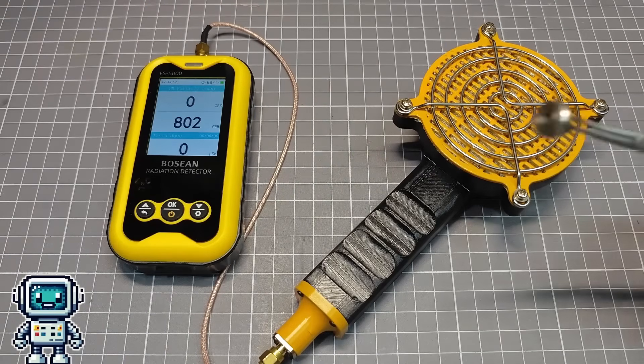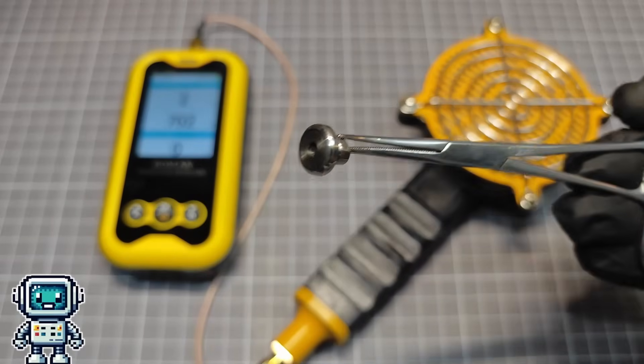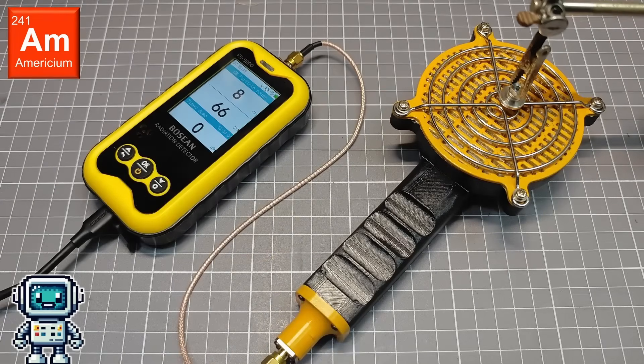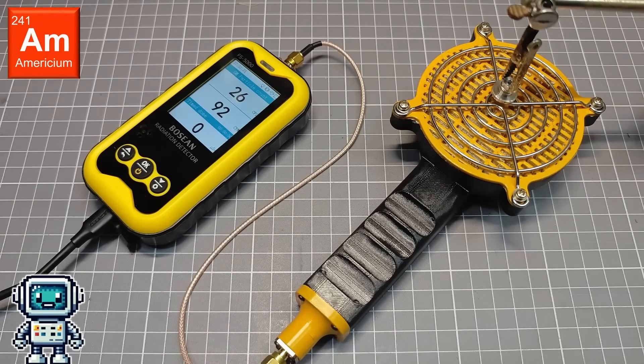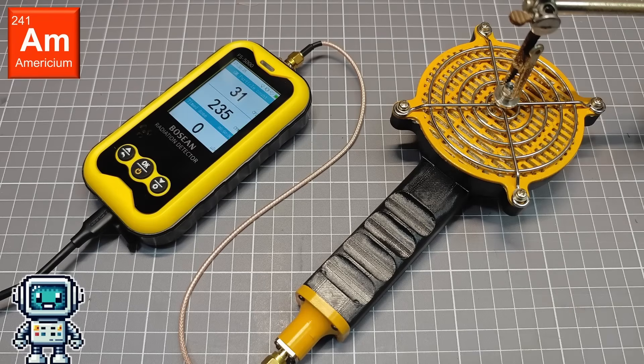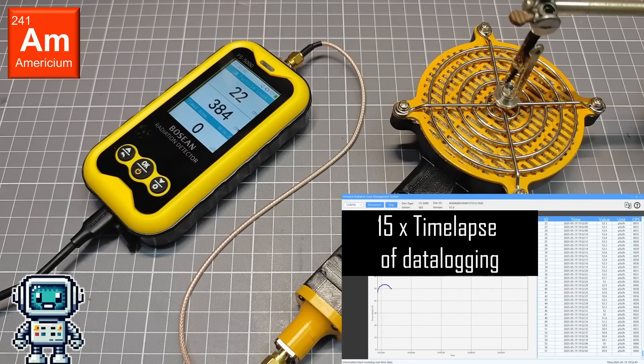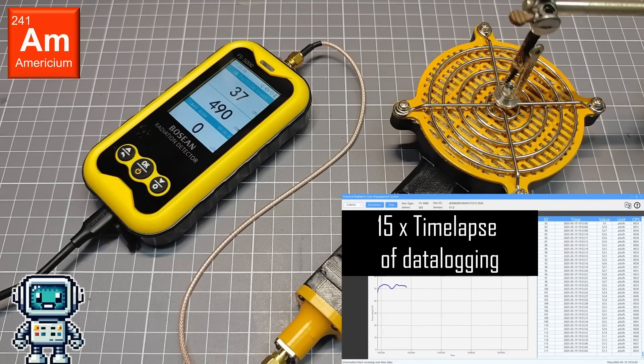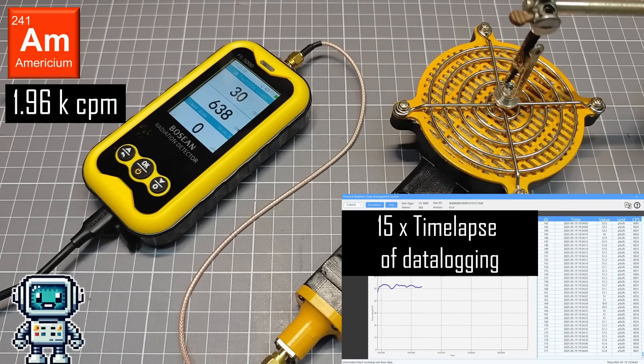Right, let's push on and measure some test sources. First, let's test with americium-241. This predominantly decays with the release of an alpha particle, but there is also a small amount of low energy gamma radiation emitted as well. We are dearly hoping that this probe is also sensitive to alpha particles, it would make it a very useful addition to our equipment. We end up getting an average count rate of 1.96 kilo counts per minute.